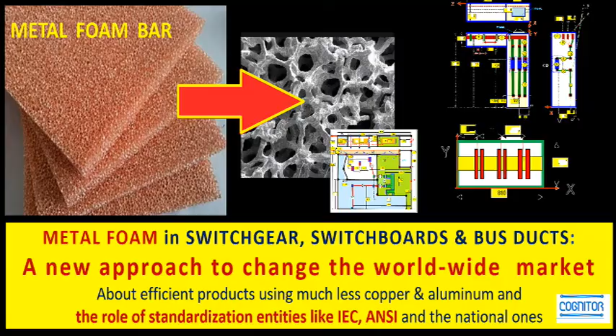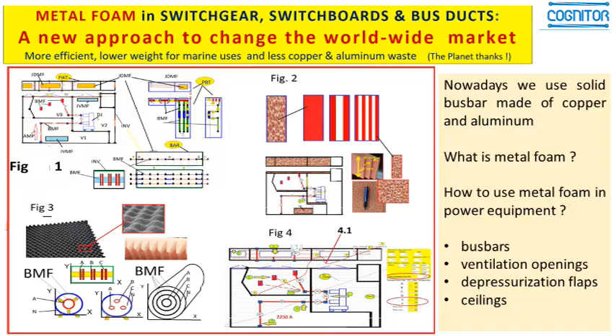In our case, we will use this in bus bars, replacing the solid bars, and in the ventilation openings, as I explained before, including the replacement of the filters that we commonly use. We also use it in the depressurization flaps, because it is a very light material and has the property of acting like some kind of arc absorber. And we can also use it in ceilings, to permit that during normal use of the switchgear, the hot air which is at the top of the switchgear flows outside, permitting lower temperatures.